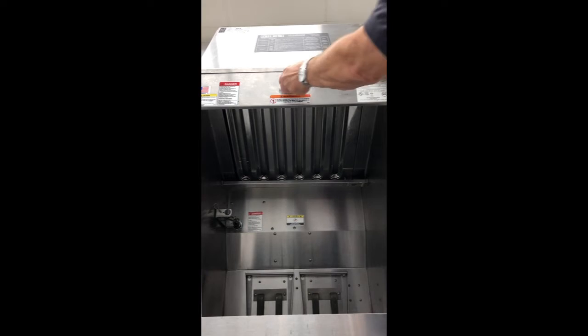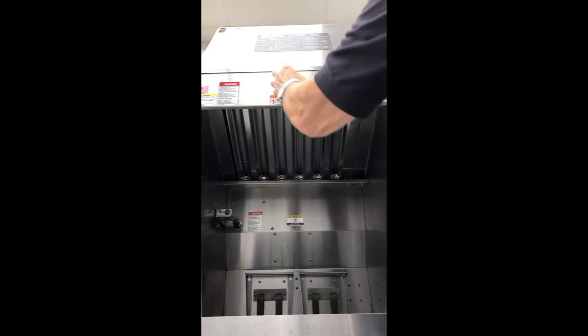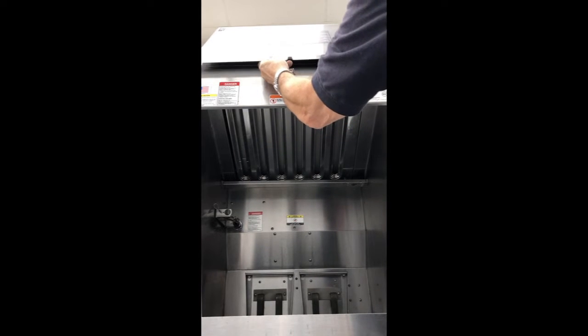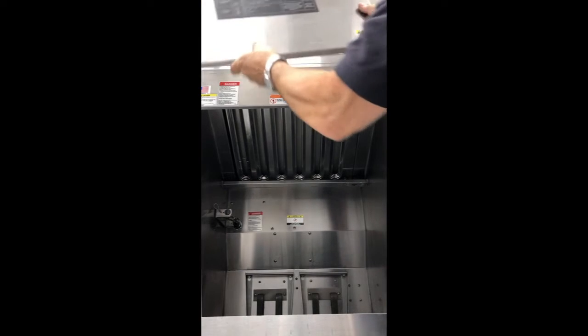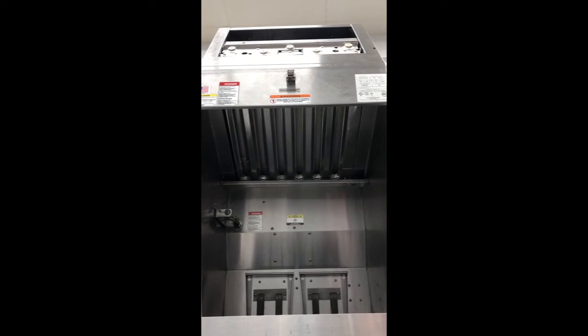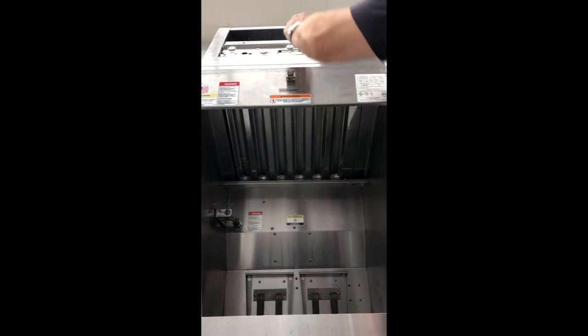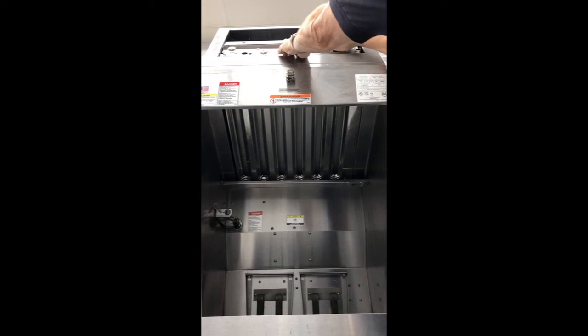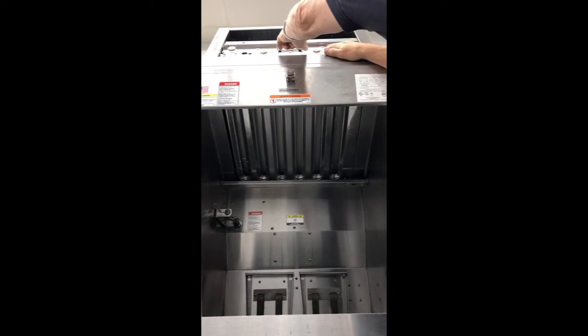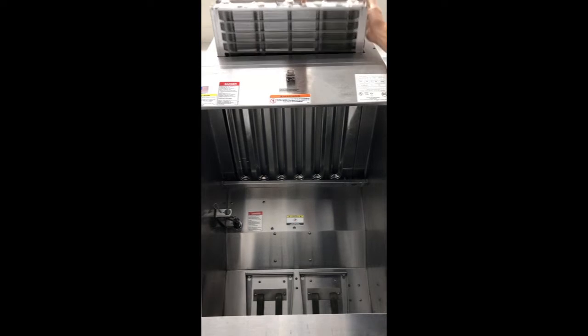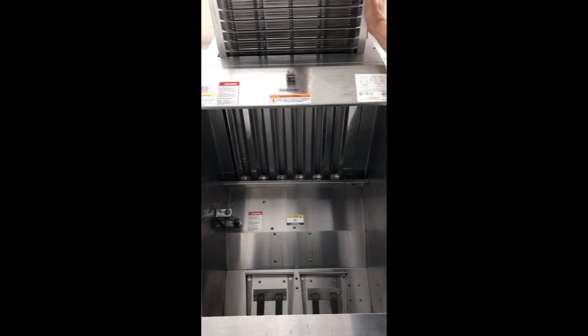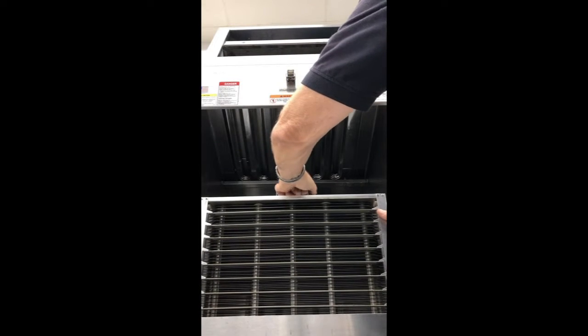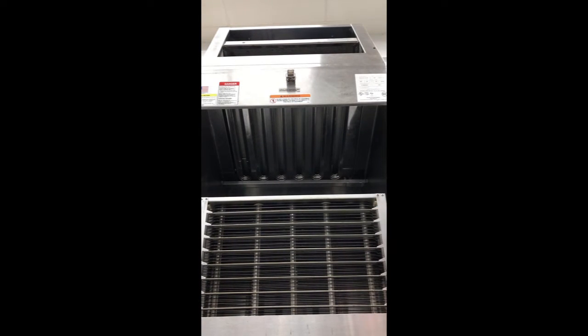Removal of the EAC filter is fairly simple. We'll undo this latch, pull this out at the bottom, slide the cover up, and it'll come right off. Set it aside. Grasp the EAC filter, charcoal filter on top, EAC filter. Pull it straight out, being careful not to catch these fins. Then you can bring it right out, set it right down here on this unit or on another table. And we're going to look at it in just a second and test it.